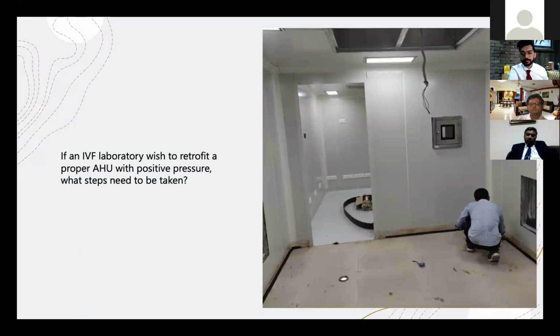So, two separate AHUs: one for the ICSI lab and one for the OT, which could also be a common AHU for the hospital. This ensures the pressure in the embryology lab is highest, so that if air exits at all, it exits the embryology lab rather than entering it. The next highest pressure is in the OT, and the lowest pressure is outside.